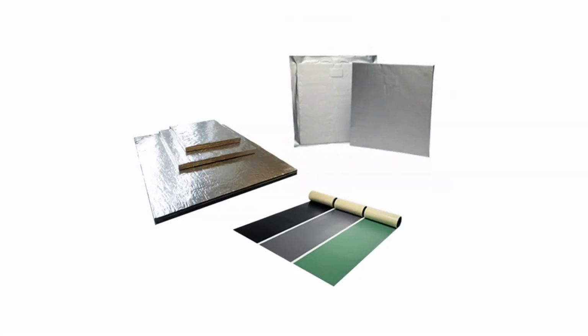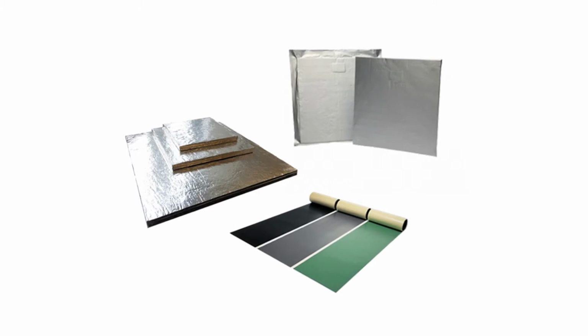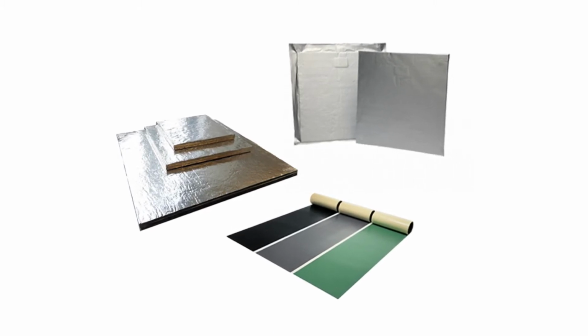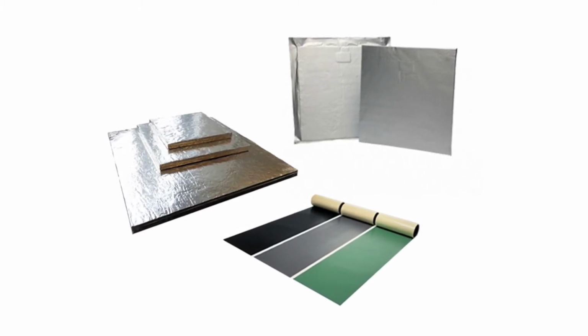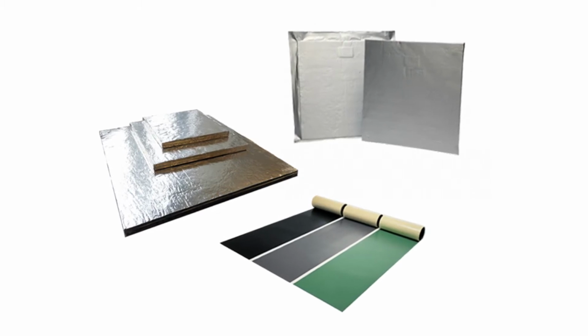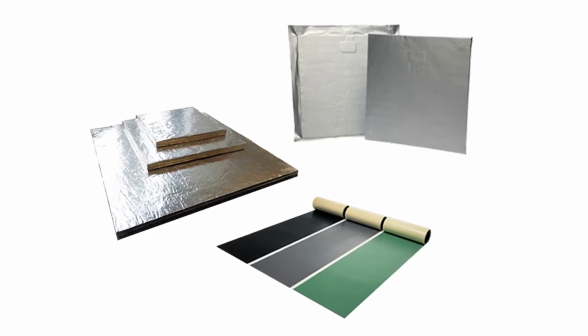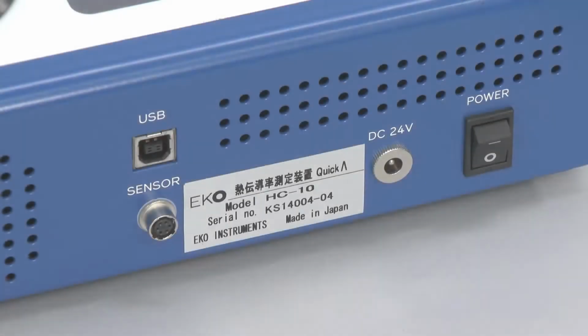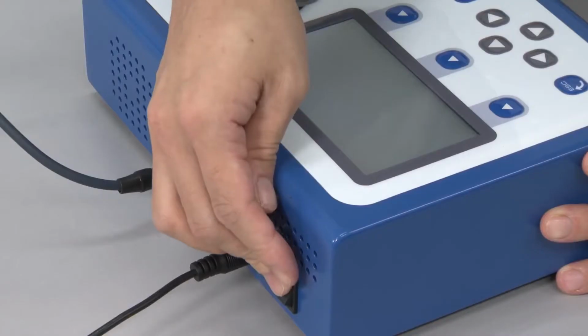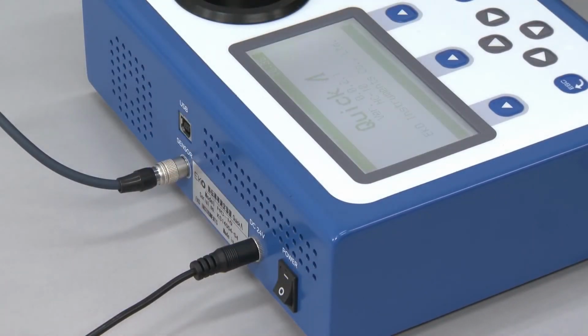Because the HC-10 is a relative measurement device, before measuring a sample, we need to calibrate the device for that type of sample. You only need to do this once for each type of sample, as you can reuse the same calibration file for future measurements. First, let's set up the unit. Plug in the power and sensor cables and turn the power on.